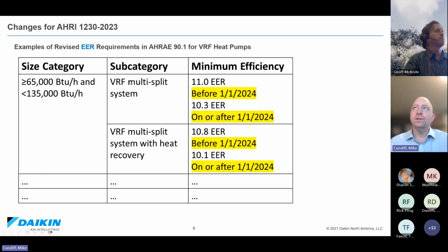To address this also, ASHRAE 90.1 has lowered all of the minimum efficiencies to take into consideration this more stringent test procedure. Before 1/1/2024, it was 11. Now it's 10.3 is the EER minimum for ASHRAE 90.1. Likewise, for the heat recovery number here below, before it was 10.8, now it's 10.1. So a little bit different.